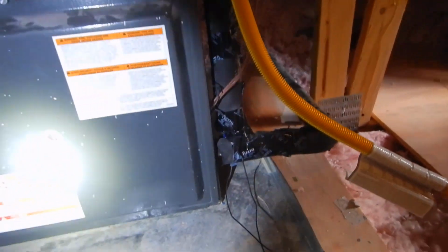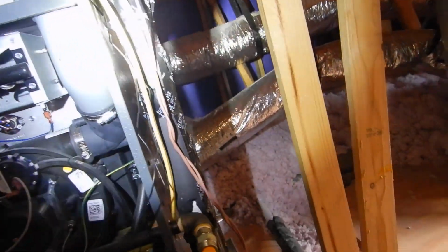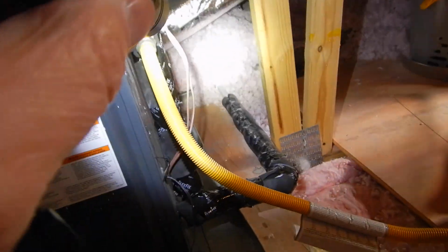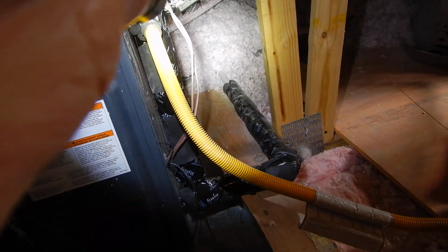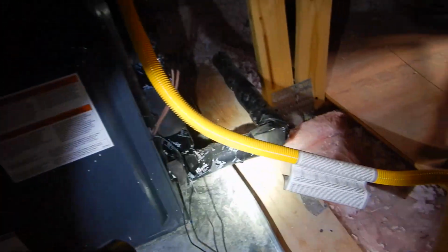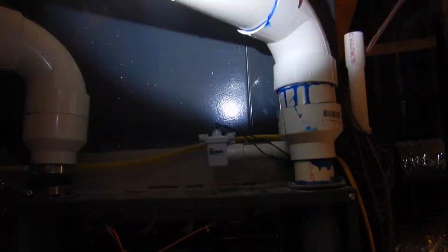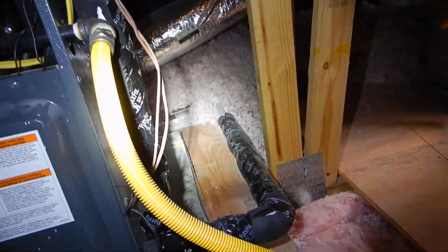Okay, so this is our safety pan. This is our safety switch. Okay, that's all we need. This is our primary evaporator drain line. We're supposed to have a P-trap on this. This drain pipe goes to the sewer. So if the sewer gases come up this pipe and go back in here, these are your evaporator coils, and then it gets redistributed all the way through your house, and everybody gets to smell the same thing at the same time. How about that?